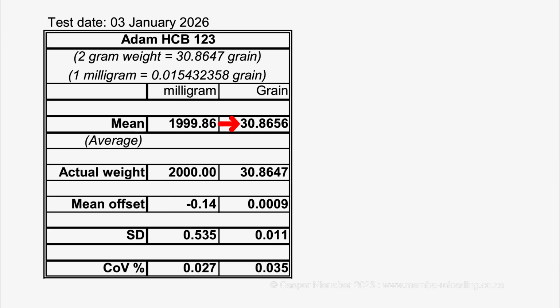The mean of 30.8656 grains is only 0.0009 grains above the true value of 30.8647 grains. The SD in milligrams is only 0.535 milligrams, well below Adam's specification of 0.8 milligrams. The SD in grains is only 0.011 grains, approximately half of Adam's specified 0.02 grains.